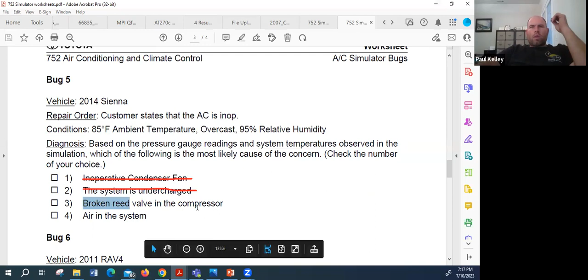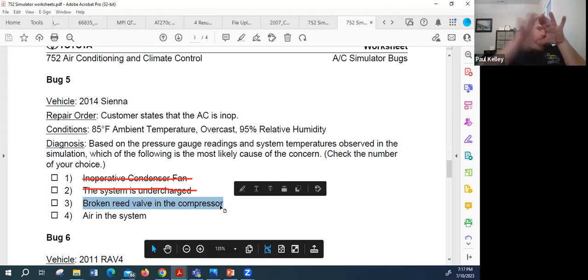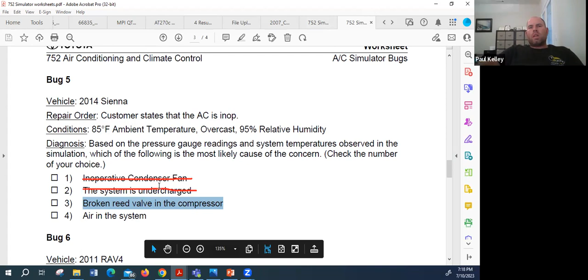So we'll go with the broken reed valve, because that's going to cause the low to fluctuate, since the compressor pushes back into the low. It's going to cause the high to fluctuate too, because the compressor draws from the high unintentionally. Cool, which puts us at 6.